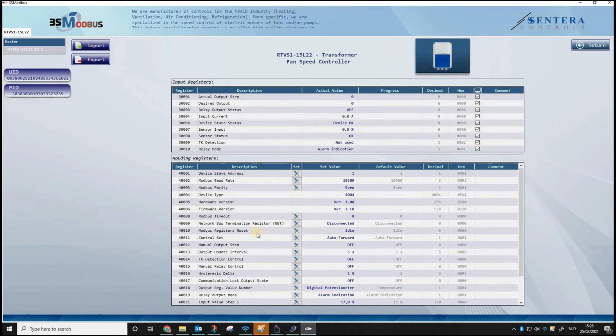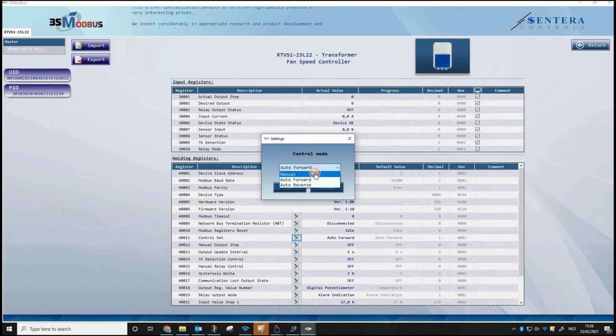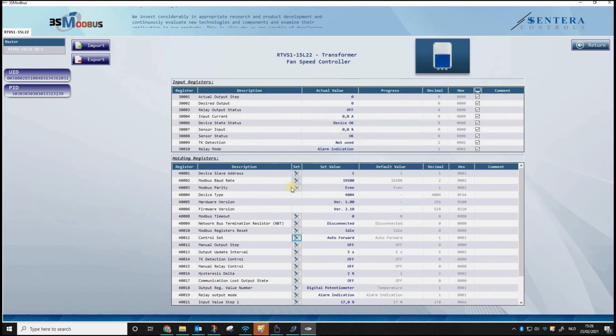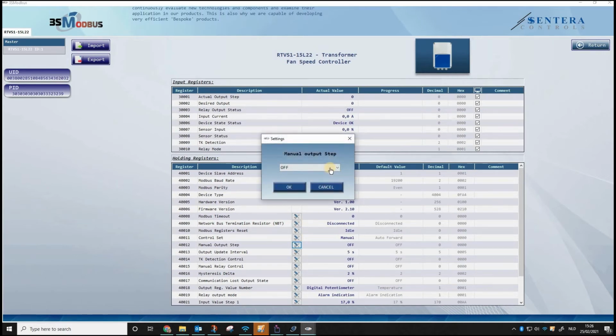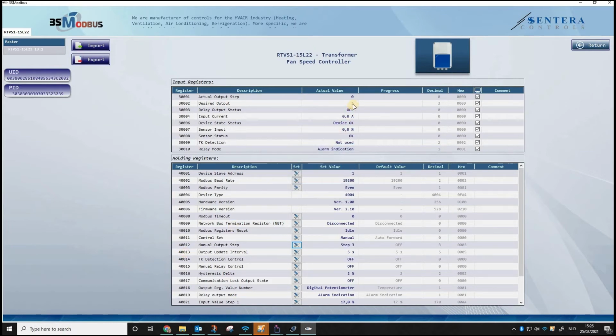If you would like to change this, we will start by putting the unit in the manual status via this parameter. After which we choose, for example, 3 as the output step. As soon as I activate this, you will see that the desired output step is step 3 and that this step is going to increase with an interval of 5 seconds as set in Modbus register 40013. 3 is the desired step.